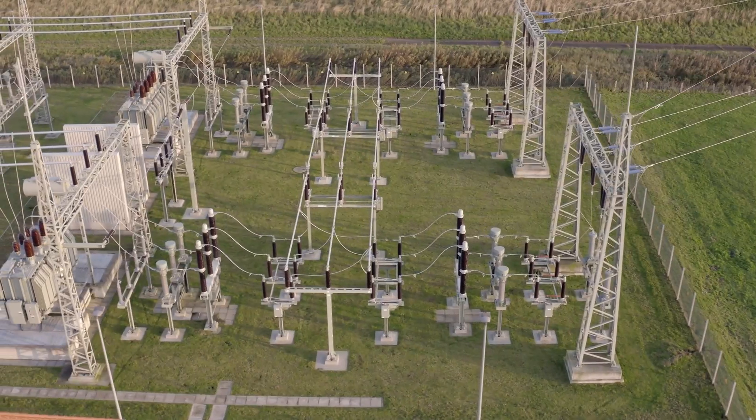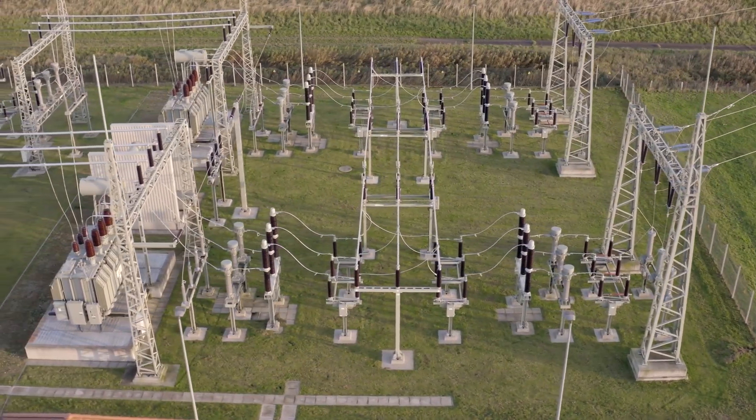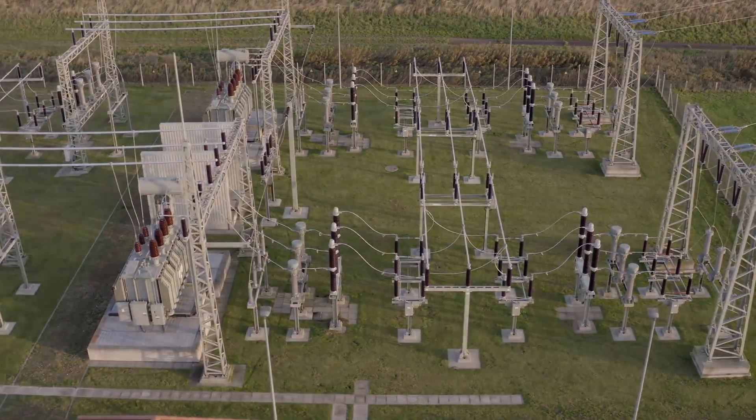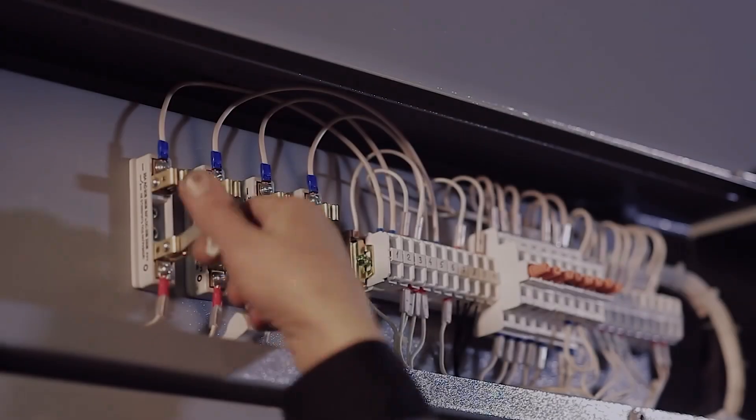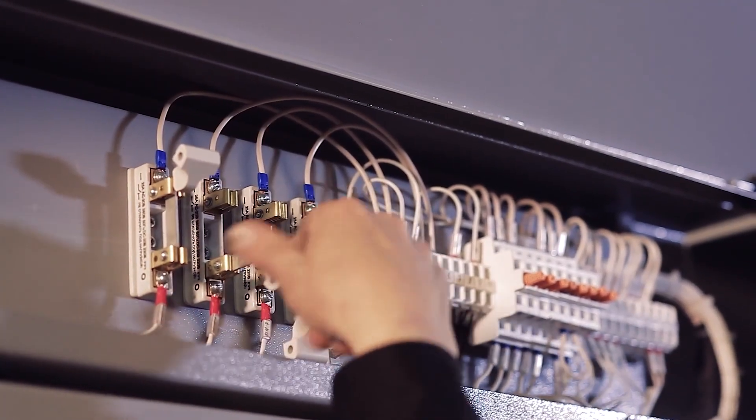While lightning is often thought of as the main culprit of surges, it's much more common to have surges as a result of switching. Some of the typical causes of switching transients include capacitor bank switching, power grid faults, and load changes.